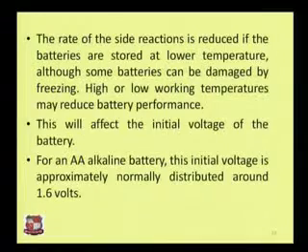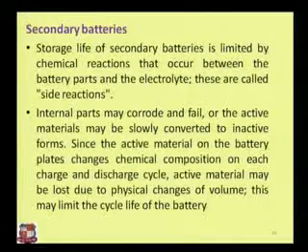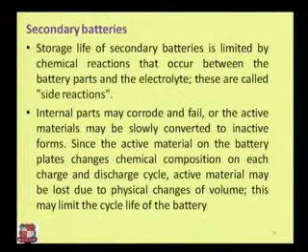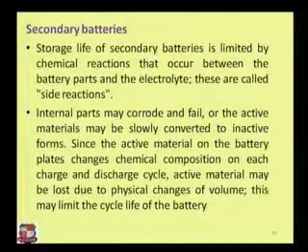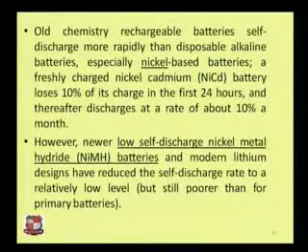The storage life of secondary batteries is limited by the chemical reactions that occur between the battery parts — electrodes and electrolytes — which are called side reactions. Internal parts may corrode or fail, or the active materials may be slowly converted to inactive forms. Since the active material on battery plates changes chemical composition on each charge and discharge cycle, active material may be lost due to physical changes in volume, which limits the cycle life.